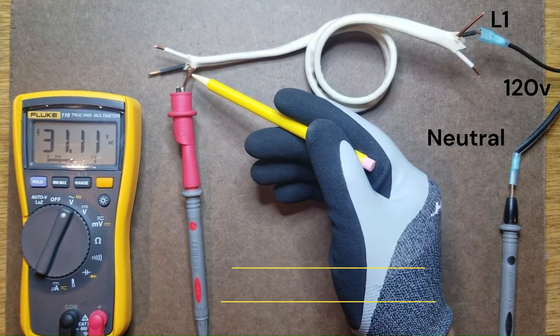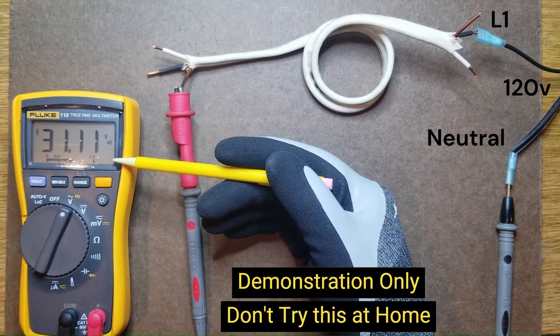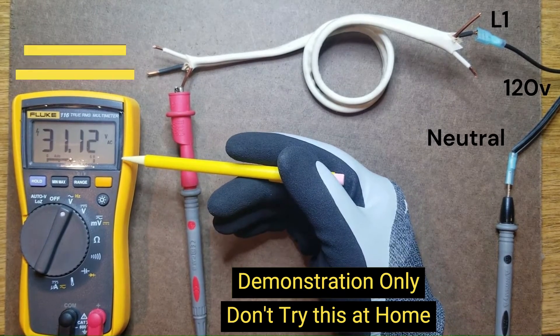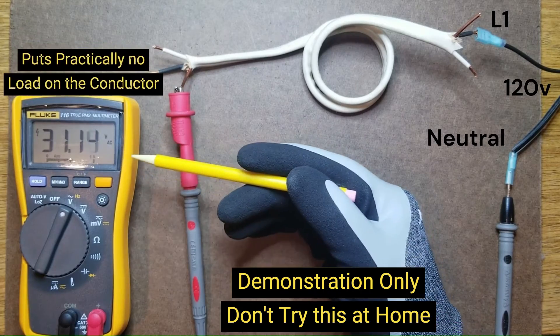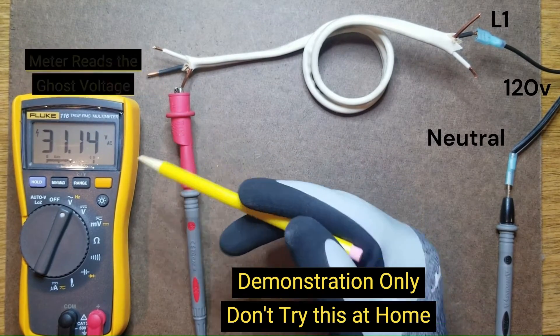This voltage has almost no ability to provide any current. However, when this meter is in regular voltage reading mode, its greater than 5 million ohm input resistance puts practically no load on the wire and thus reads the ghost voltage.